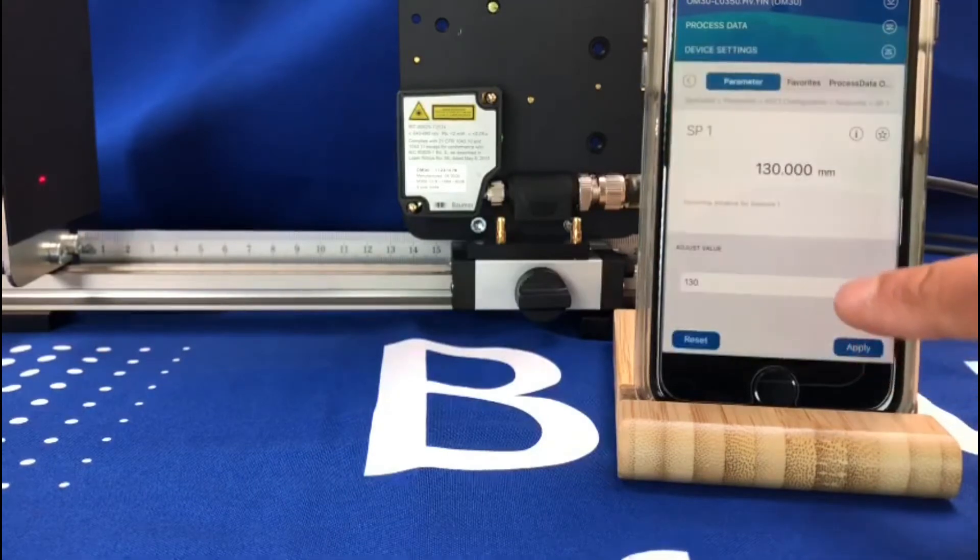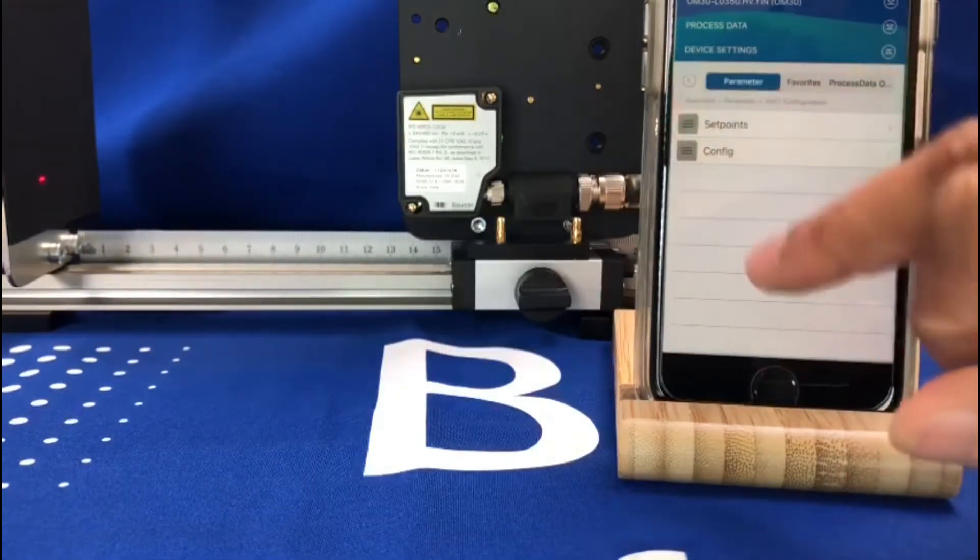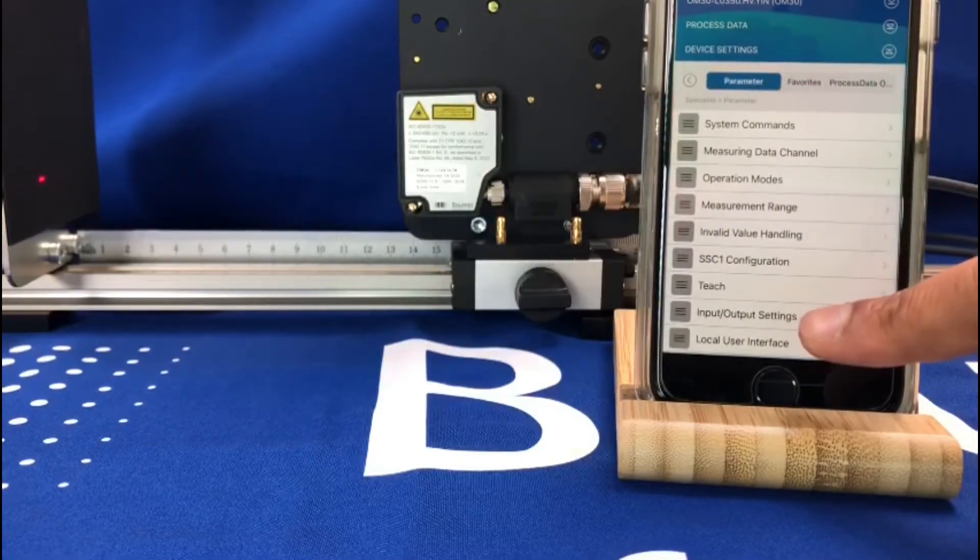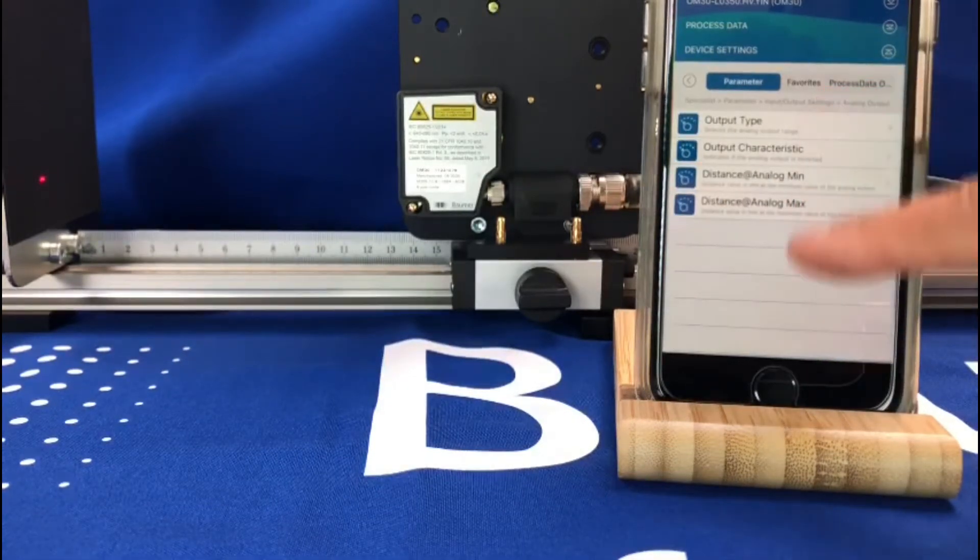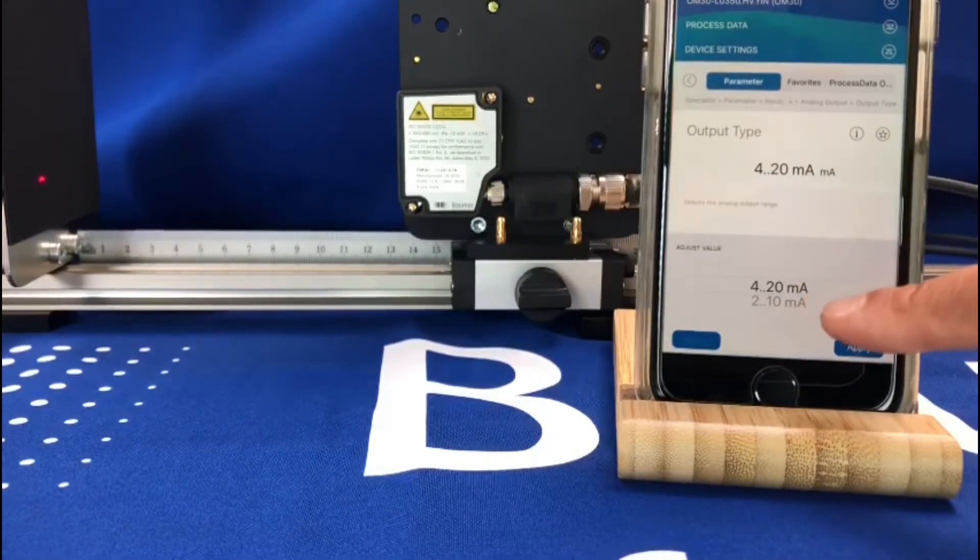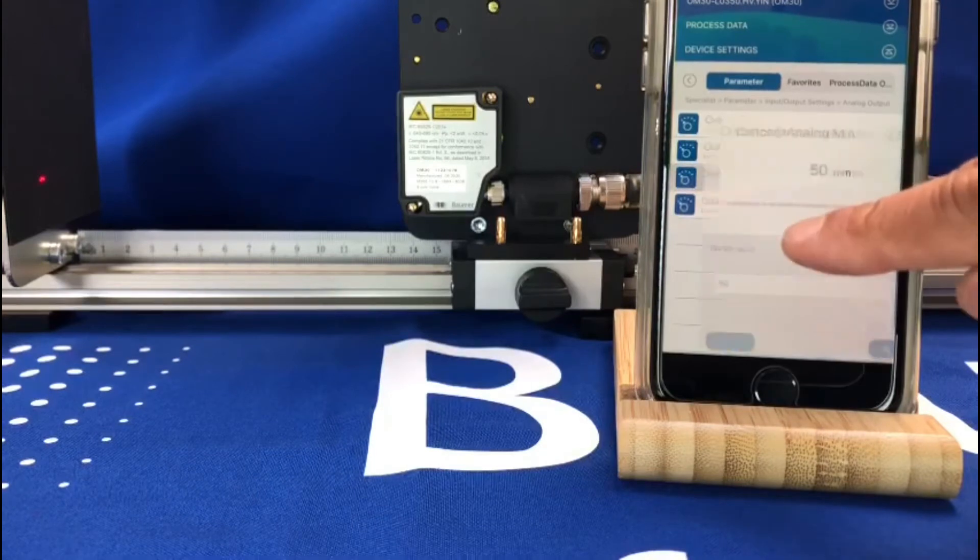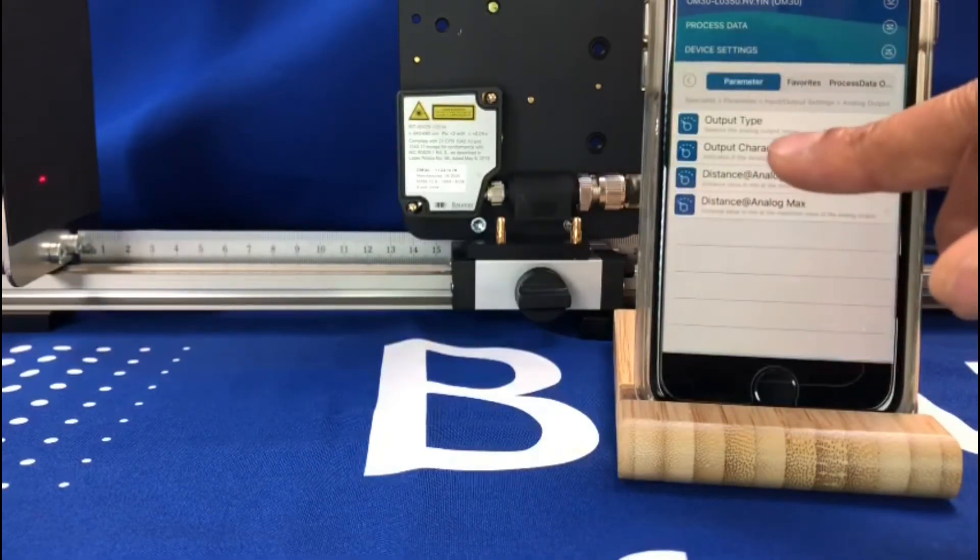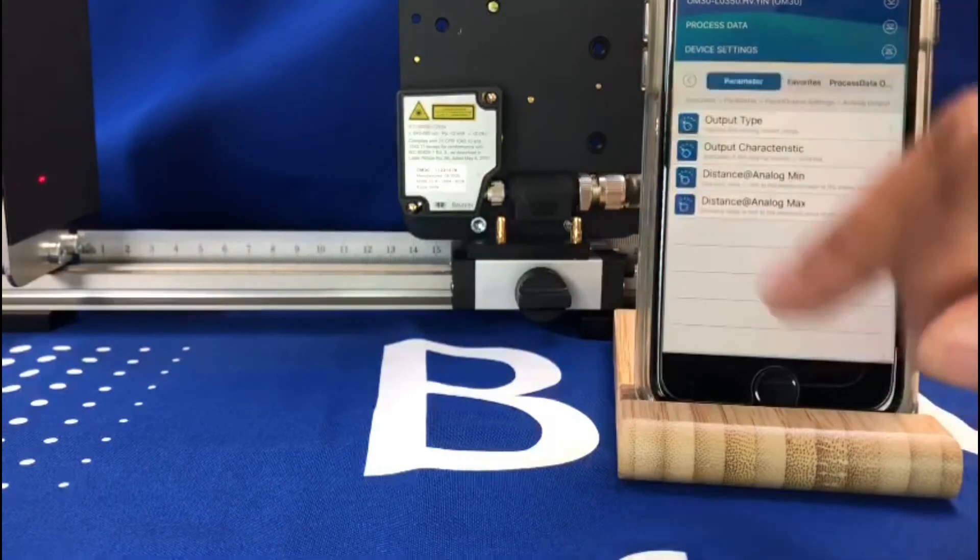You can also do other types of setup, so if you want to set the analog range, for example, you can go to the analog output. You can set whether you want it to be 4 to 20 milliamps or 2 to 10 milliamps. You can set the minimum distance and maximum distances. So out of the box it does 50 to 350 mil, but you can change that to whatever you want and also invert it or keep it not inverted as it is out of the box.